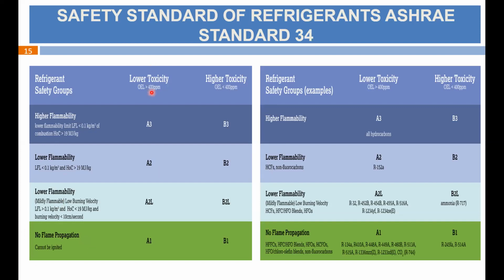So the best will be A1 kind of refrigerant, which has lower toxicity and no flame propagation, so it is not a flammable refrigerant. Similarly, the worst refrigerant will be B3, which has higher toxicity as well as higher flammability. These diagonally opposite categories are the best and the worst. The intermediate ones are like A2, B2, which have lower flammability. This lower flammability is also measured in terms of the lower flammability limit. We call it LFL.